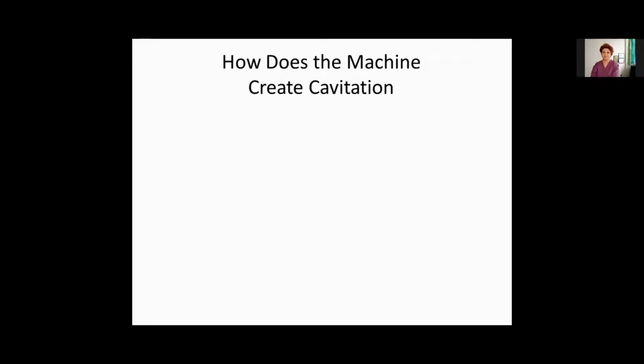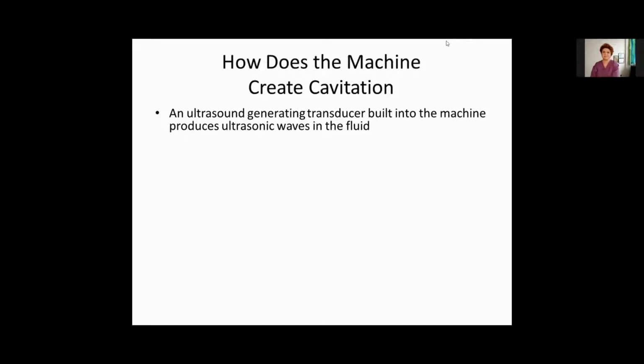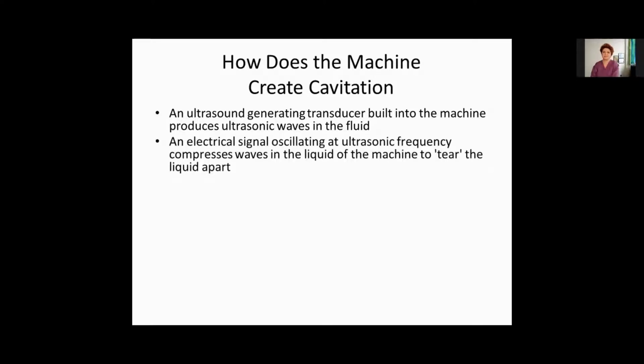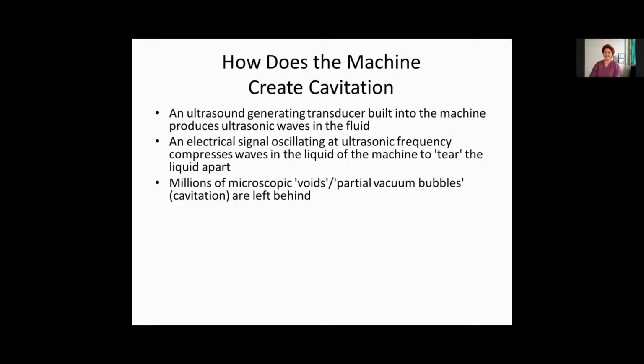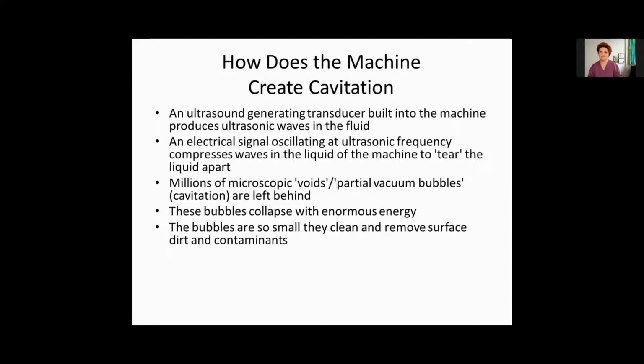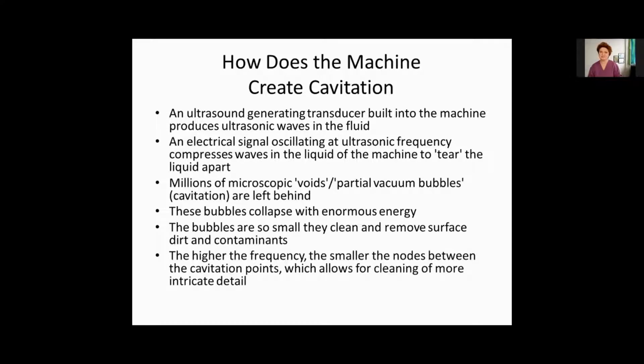So how does a machine create cavitation? An ultrasound generating transducer built into the machine produces ultrasonic waves in the fluid. An electrical signal oscillates at ultrasonic frequency, compresses waves in the liquid of the machine to tear liquid apart. Sounds cruel. It does, doesn't it? Millions of microscopic voids or partial vacuum bubbles are left behind, and that's the cavitation. These bubbles collapse with enormous energy. The bubbles are so small they clean and remove surface dirt and contaminants. The higher the frequency, the smaller the nodes between the cavitation points, which allows for cleaning of more intricate detail.